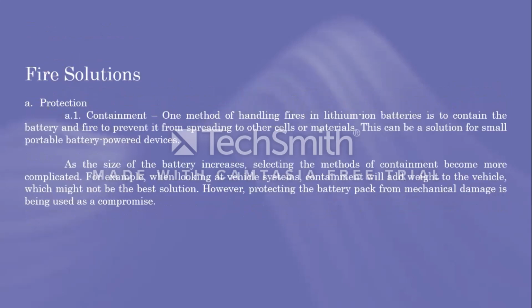Letter B. So next up is the gas detection. Off-gassing occurs early in cell or battery failure. Some battery cells provide vents specially intended to release the overpressure that may develop within individual cells as a result of abuse or failure. Others may expand to accommodate the degree of off-gassing, but at some point this may burst, perhaps along a seam or pre-designed weak point.